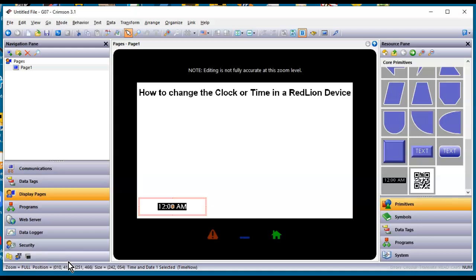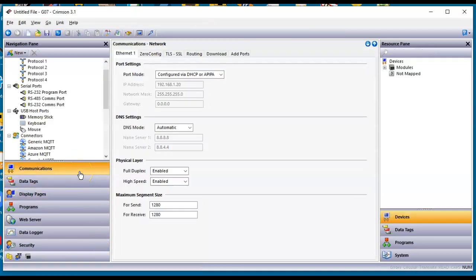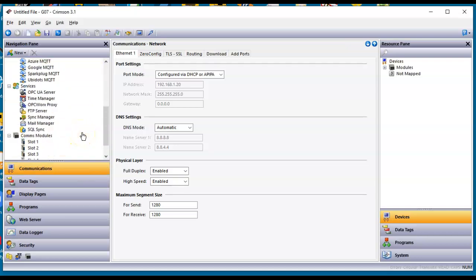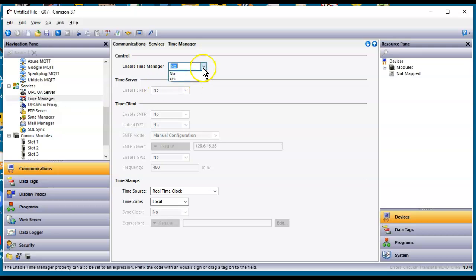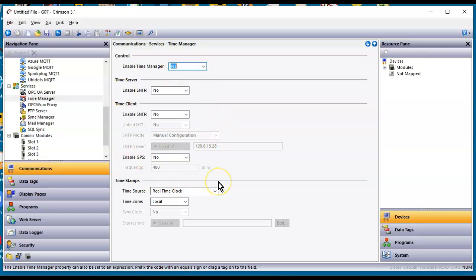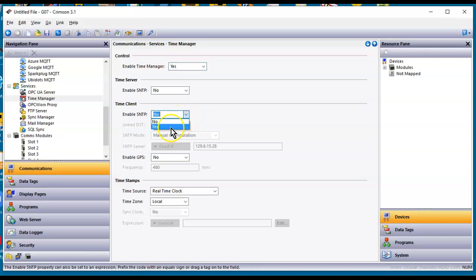And the third method that you can do for a clock thing is a little more intense. But over in the left-hand side in Communications, over here in Communications, if I slide down to the Services section, and here in the Services section you can see there is a Time Manager. Now in this case, you can use this if you're connected to the internet. You can enable the time manager and set up some time client here where it would get the time from an SNTP server, and so you can set this up to get the time from there. Great.